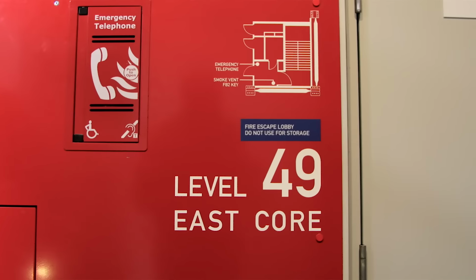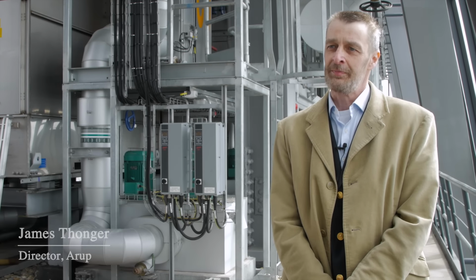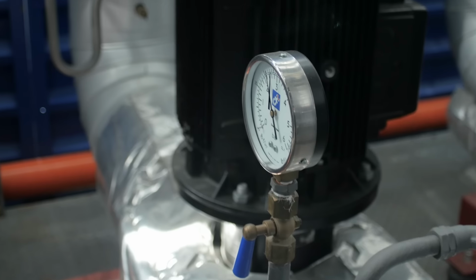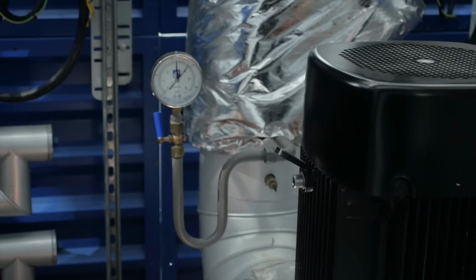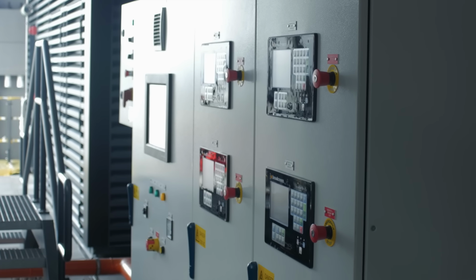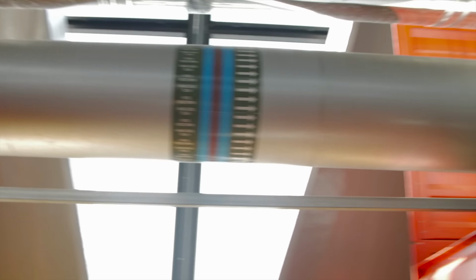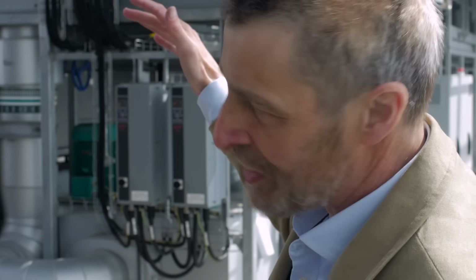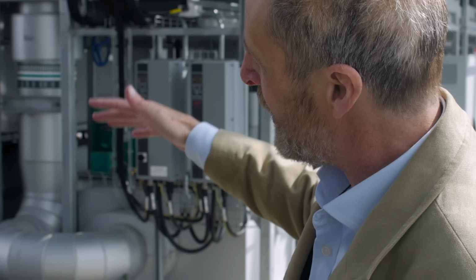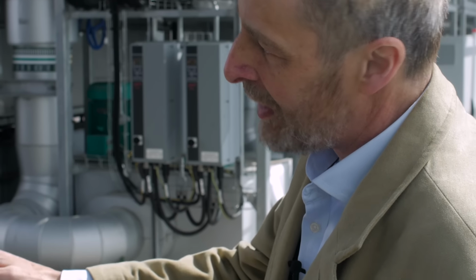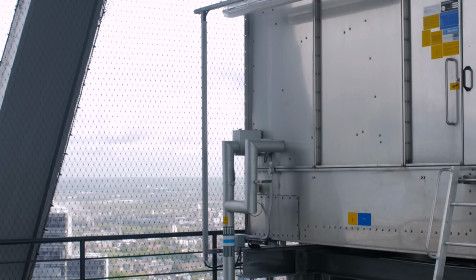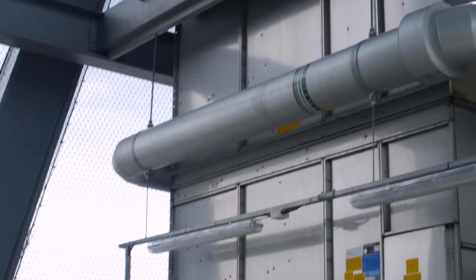We're here on the 49th floor of the Leadenhall building. It's at the base of where the cooling towers are. Below us are 3 levels of plant room, and above us is the cooling tower level of the discharge, and above that there's a cooling cradle. So what we have here is plate heat exchangers, which are changing the chilled water from a condenser water system in the basement, converting it into an evaporative cooling system. In the steel boxes you've got a cooling medium, which is water, going through a large drop. And it allows fresh air from the outside of the building to come in and get drawn through the water, which evaporates. And that is the main cooling mechanism for the building.